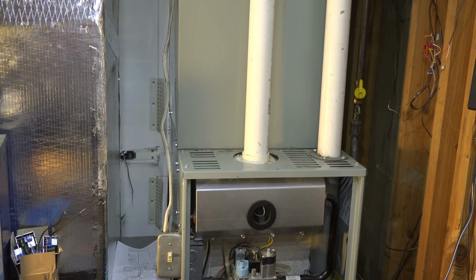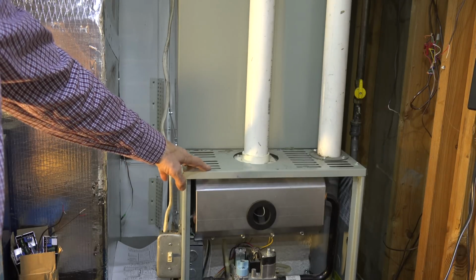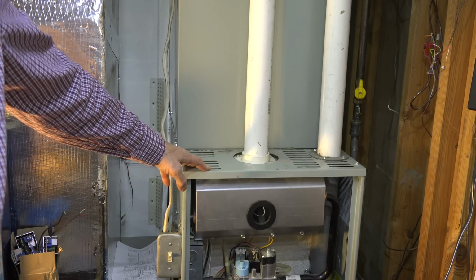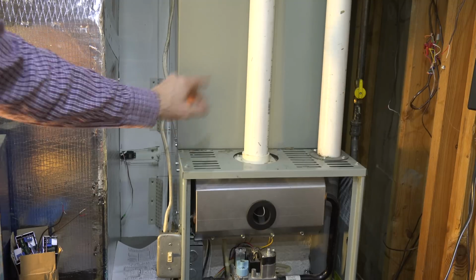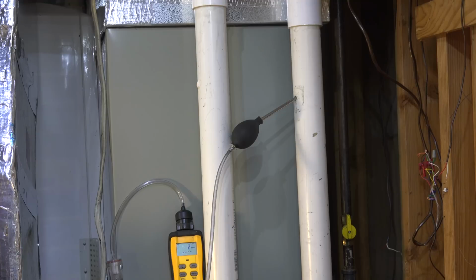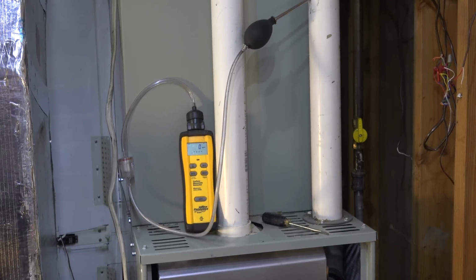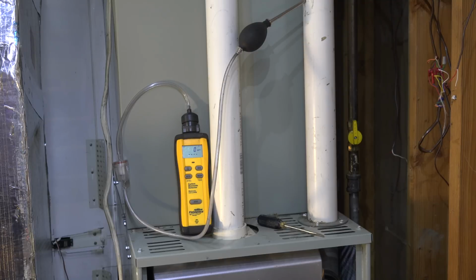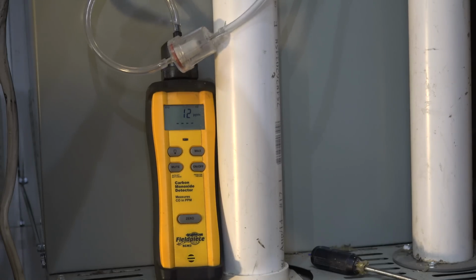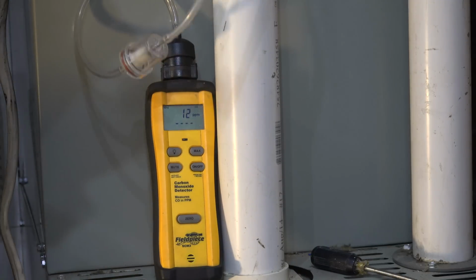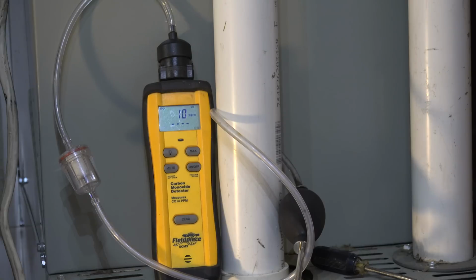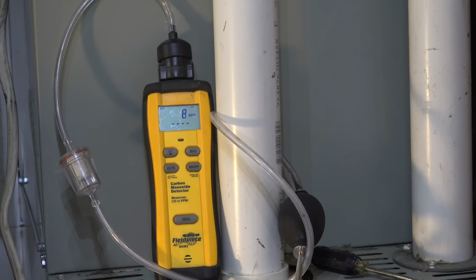Now, let's assume in the ductwork I had higher concentrations of CO. The next thing I'm going to do, because now I'm suspicious, is check the CO in the vent pipe. Here's my furnace running, and I have the CO detector in. I have to pump this old boy, but let's go ahead and pump this and see what happens. Looks like I'm settling at about 12. That's well within any kind of limits. Actually, I see a lot of them that I don't really like at 100 parts per million, but I have seen them that high and still be operating pretty close. I'd like it lower than that.